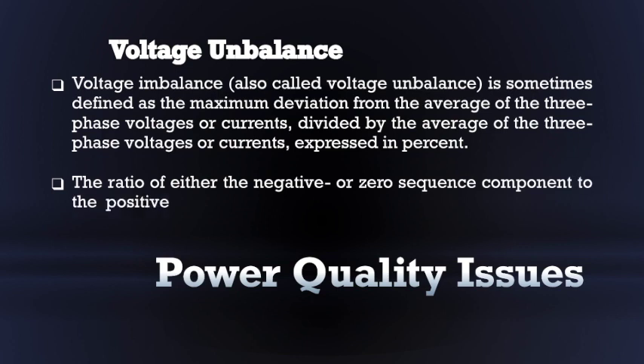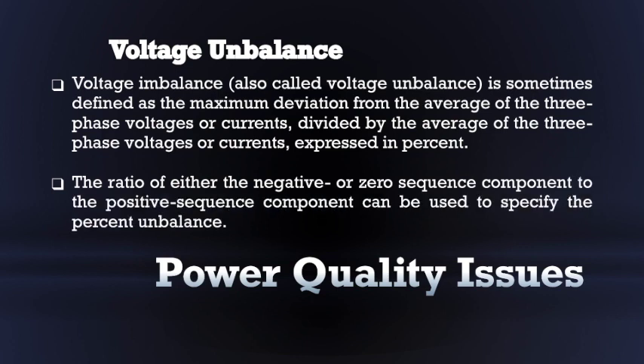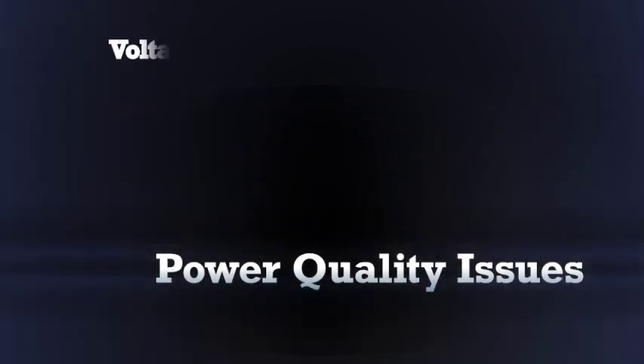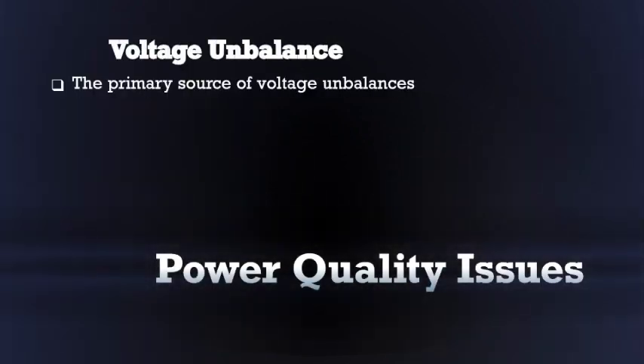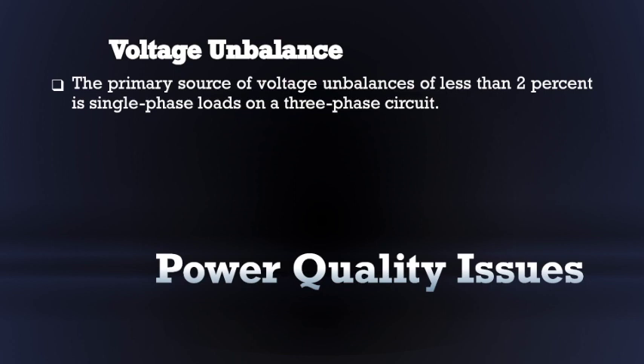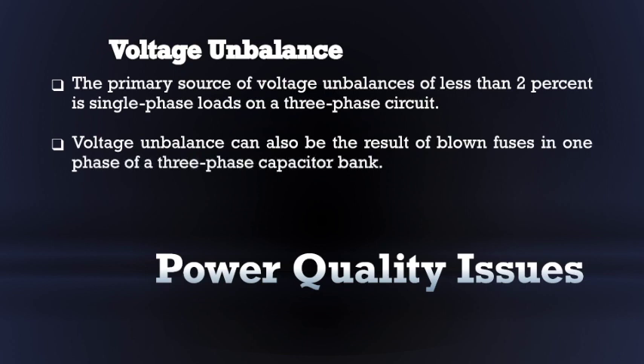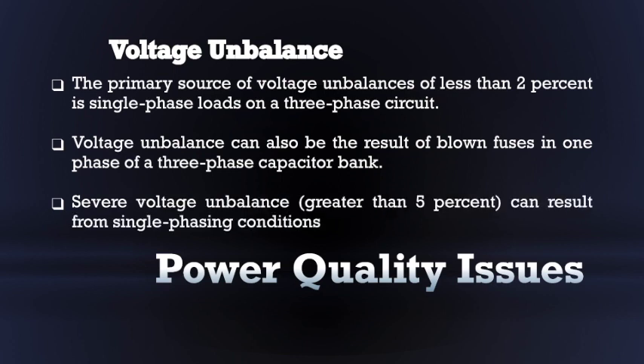Also, the ratio of either the negative or zero sequence component to the positive sequence component can be used to specify the percent unbalance. The primary source of voltage unbalance of less than 2% is single-phase loads on a three-phase circuit. It can also be the result of blown fuses in one phase of a three-phase capacitor bank. Severe voltage unbalance can result from single-phasing conditions. You can see the figure.